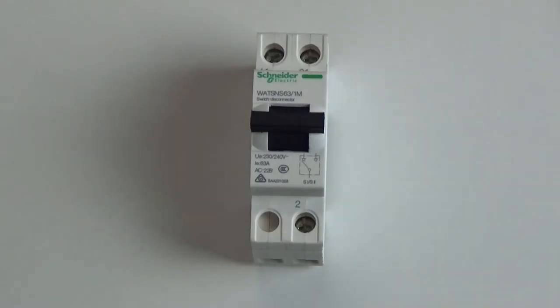Another test you can do is on the top right hand corner. That should be connected to grid. So if you switch the mains off, that should go dead as well. And that's a couple of easy tests to work out if you've wired it in correctly or not. Nice and easy.